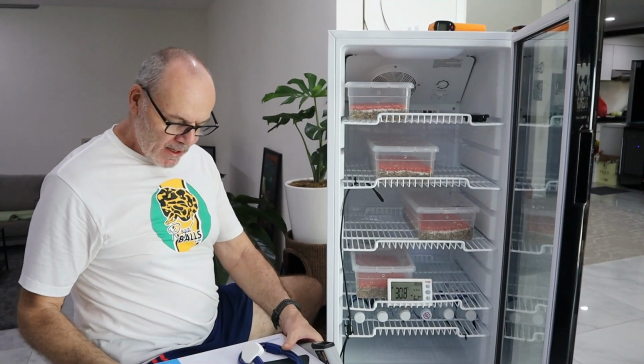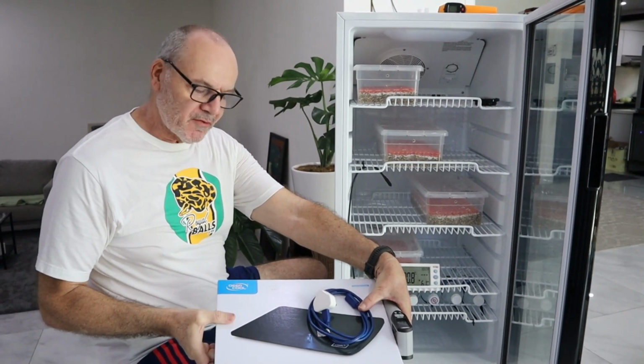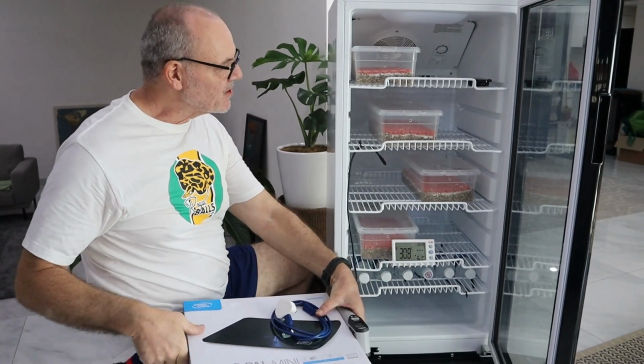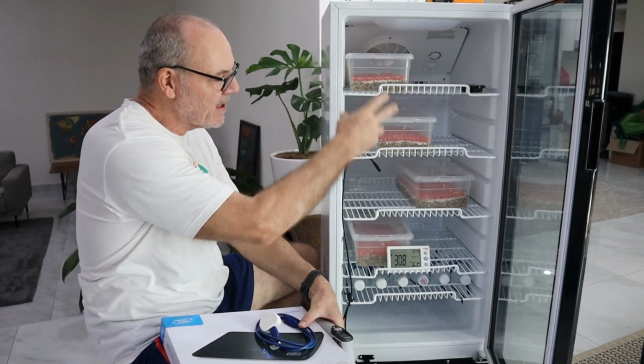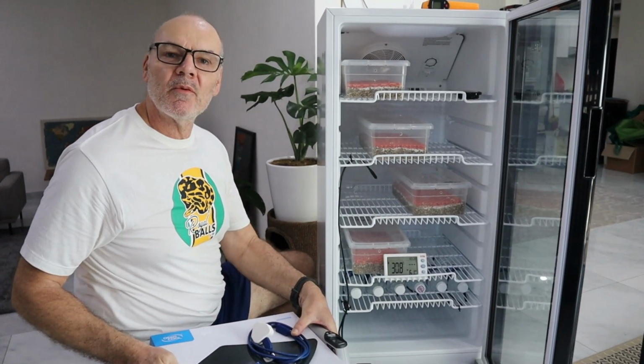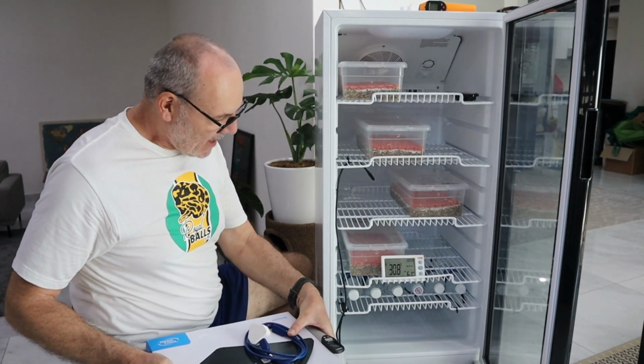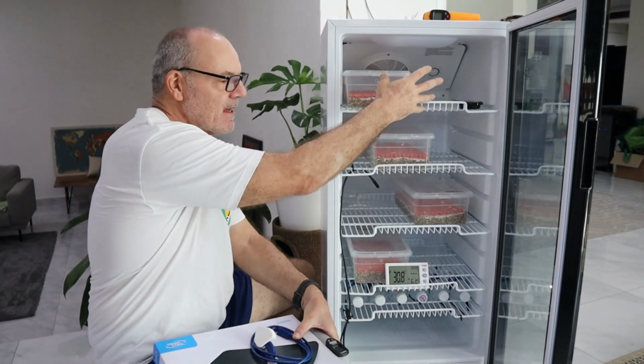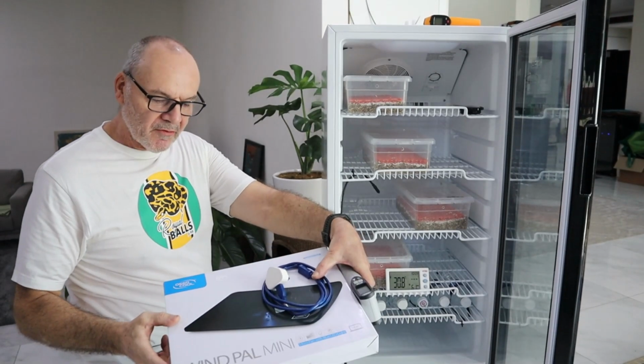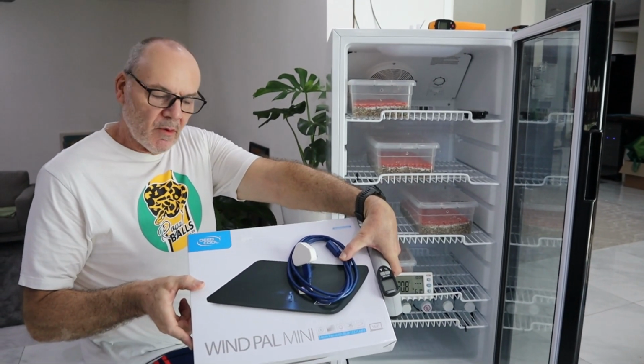So we're going to put the fan in for another 24 hours and see if that makes a difference to the temperature gradient that we're seeing in here. I'm already fairly happy with the way the incubator is working. I'd just like to clear this dead zone at the top. So we'll come back in about 24 hours after I've put the fan in, and we'll have a look and see what difference that made.